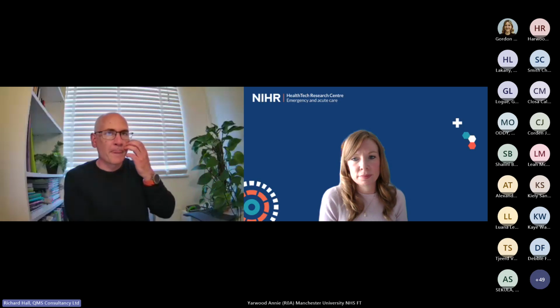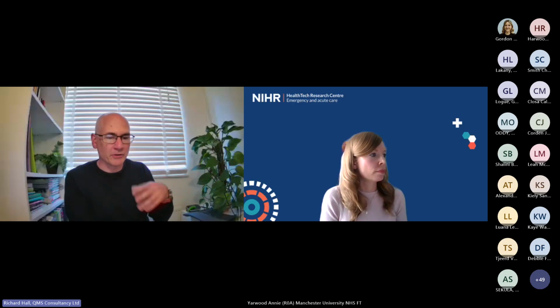One of my very last slides, in the next session, is about software and the importance of 3 decimal place version control. So rather than having version 25, you might have version 0.1.7 or something. So if you're on the market and the notified body's already given you a CE mark, and you get some customer feedback or a complaint that says there's something wrong with the product, it might be a patch that you put onto the software to keep it working as intended.